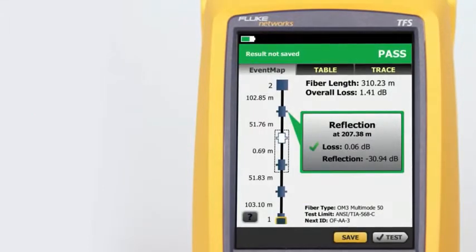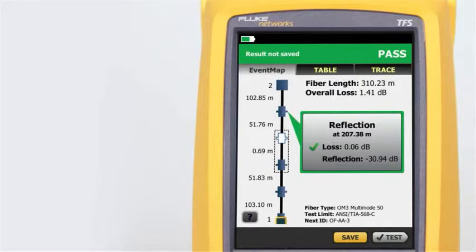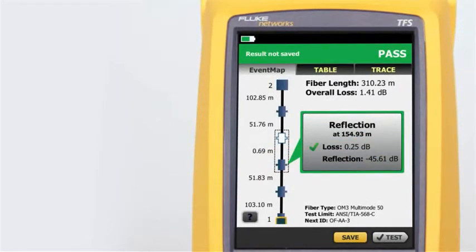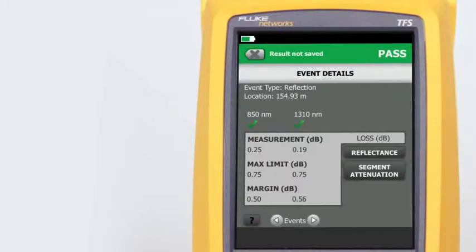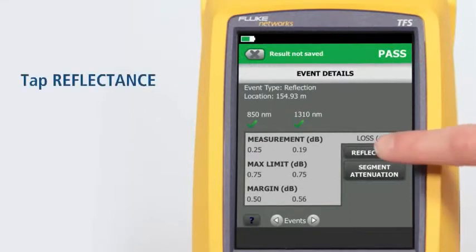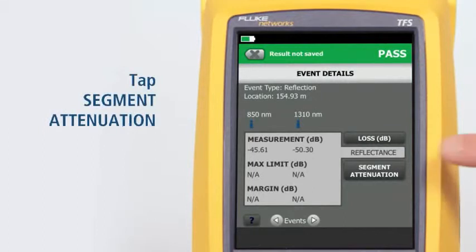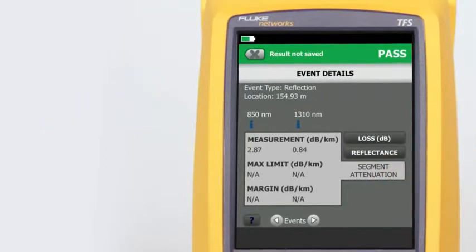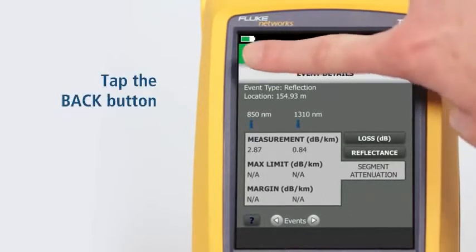OptiFiber Pro's advanced logic automatically interprets the trace information to create a detailed map graphically depicting all connectors, splices, and anomalies with easy-to-understand icons. By tapping on any color-coded icons — red/green for pass/fail — we can view the event's summary information, and view any event's details by tapping its summary information bubble. The event's loss measurement and margin details are shown first. Tapping Reflectance allows us to view the reflection measurements, and tapping Segment Attenuation shows the measurement of the fiber segment prior to the event. Tapping the back button takes us back to the Event Map.